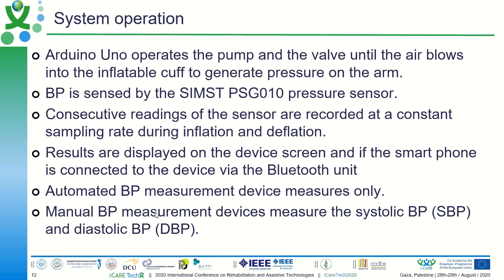The automatic or electronic blood pressure measurement system, as the one we implemented, measures only mean arterial pressure (MAP). It does not measure systolic or diastolic blood pressure directly. Only manual devices measure systolic and diastolic. However, this is not a big deal, because what we are interested in is MAP, and there are algorithms which extract systolic and diastolic blood pressure from the MAP.